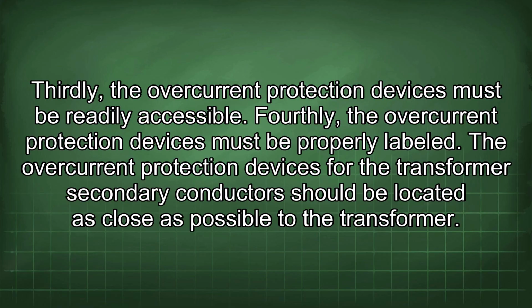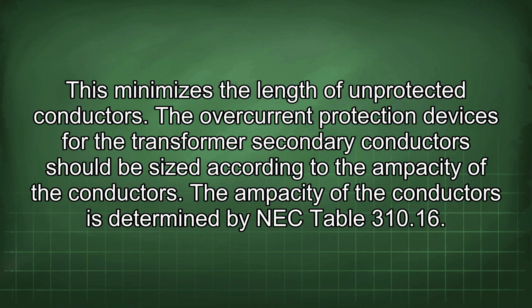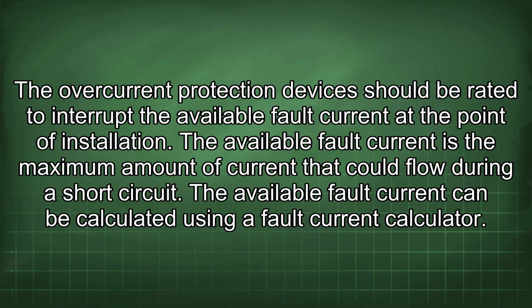The overcurrent protection devices for the transformer secondary conductors should be located as close as possible to the transformer. This minimizes the length of unprotected conductors. They should be sized according to the ampacity of the conductors. The ampacity of the conductors is determined by NEC Table 310.16. The overcurrent protection devices should be rated to interrupt the available fault current at the point of installation. The available fault current is the maximum amount of current that could flow during a short circuit. The available fault current can be calculated using a fault current calculator.